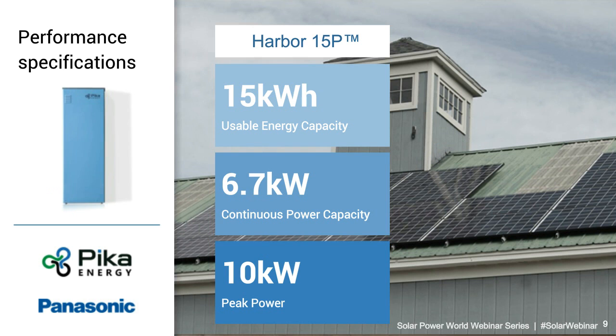Some performance specifications here. So the Harbor Smart battery is available in 2 models. And the Harbor 15P has 15 kilowatt hours of usable energy capacity. So 100% depth of discharge and 15 kilowatt hours available in the 15P with a continuous power of 6.7 kilowatts and a peak power of 10 kilowatts. And this is really important because when you're using the Energy Island system, and you've got the transformerless inverter that can use its full capacity for islanded loads, and you've got this battery that can peak at 10 kilowatts.